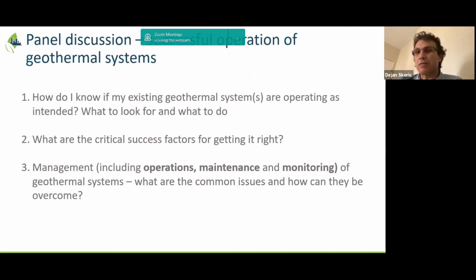I think it's crucial to have access to the data. The building automation system has to be connected, and all the points need to be trended and logged so you can remotely access them and have the history. From the ground, you need to monitor the temperatures going into and out of the ground, and monitor the flow unless it's really standard and not variable. I'd always recommend having an energy meter on the ground that analyzes the data, calculates the BTUs and kilowatt hours used, and can predict the performance of the ground source heat pump and ground heat exchanger, the bore field, over the next season or next couple of years.